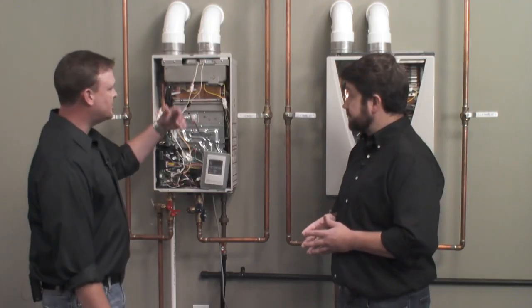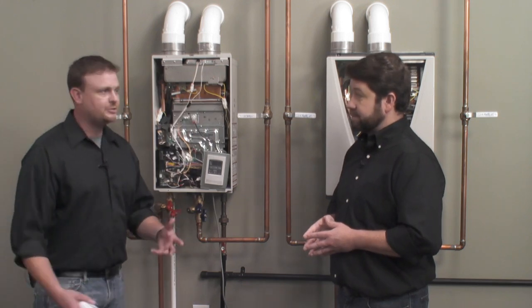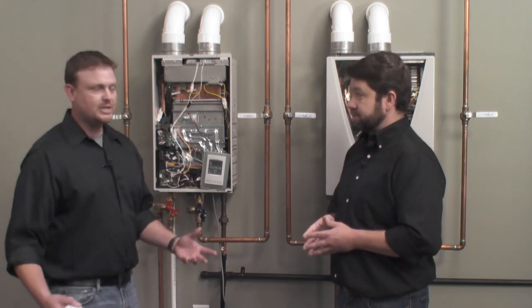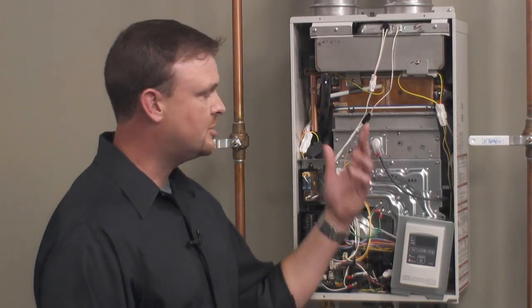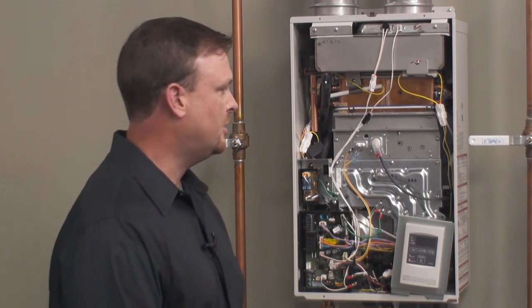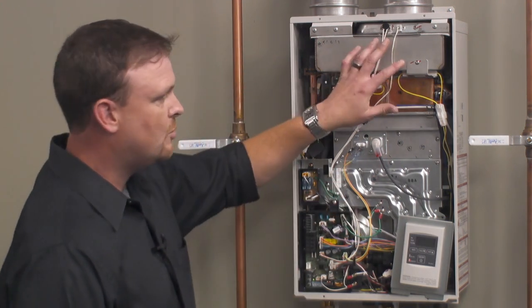Typically, whenever you're starting to see higher flue temperatures, that may mean the heat's actually not going into the water. You may have a blockage or something in your heat exchanger. It may need to be cleaned from time to time. But yeah, so we've got dual safeties here.